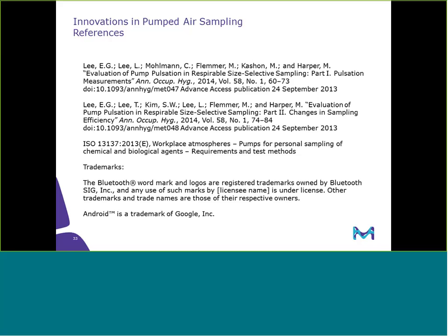What makes the calibration of the pump a little bit more interesting is that it's done over multiple points. So it's not just a few points or a handful of points. It's over the pump's flow rate range, and then that calibration file is downloaded into the pump by the manufacturer or whoever is doing the recertification. So the customer really never sees or has control over changing any of the calibration in the pump itself.